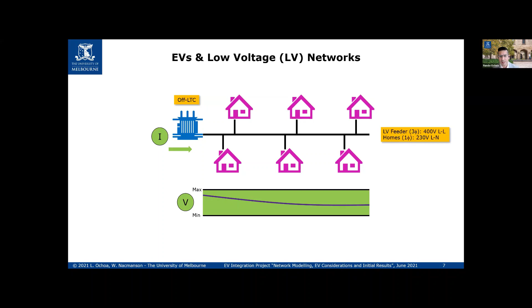The thing is, with electric vehicles there can be an excess of demand during the peak of those houses, and that coincident peak can create a much larger peak, meaning larger voltage drops and larger currents. That's not a problem per se, but if this excess demand is not within the design values used for that circuit, we'll have problems—voltage drop and thermal problems. Our conductors, transformers, and assets in general won't be able to handle the corresponding flows. That's the basic challenge we have with electric vehicles.